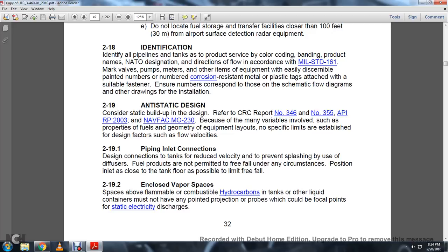219.1 Piping inlet connection. Design the connection to tanks with reduced velocity, preventing splashing by using diffusers. The fuel products are not permitted to free fall under any circumstances. Position the inlet as close to the tank floor as possible to limit the free fall.